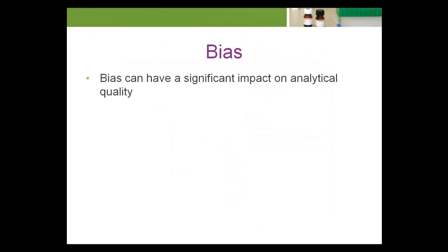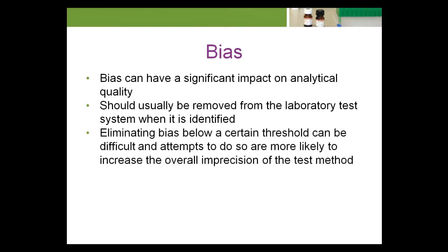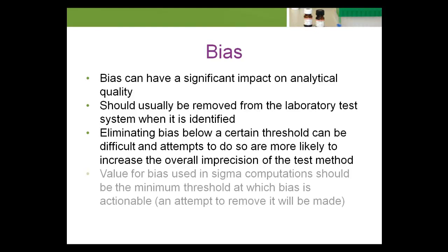Bias can have a significant impact on analytical quality and should usually be removed from the laboratory test system when it is identified. However, eliminating bias below a certain threshold can be difficult, and attempts to do so are more likely to increase the overall imprecision of the test method. In general, the value for bias used in sigma computations should be the minimum threshold at which bias is actionable — that is, the level at which an attempt to remove it will be made.